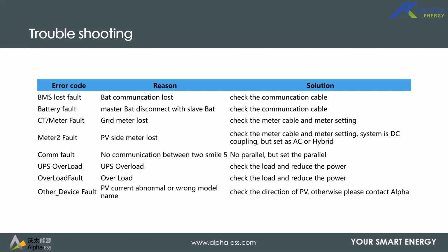This usually happens when installers mix power cables and comms cables together, which causes noise and all that. You might get this fault more often because of that. So when you run your comms cable, please run it separate from power cables to avoid continuous disconnects of the grid meter. And on the initial install, when it gives this fault, usually check if your cable is correctly crimped and if it's wired to the correct port.